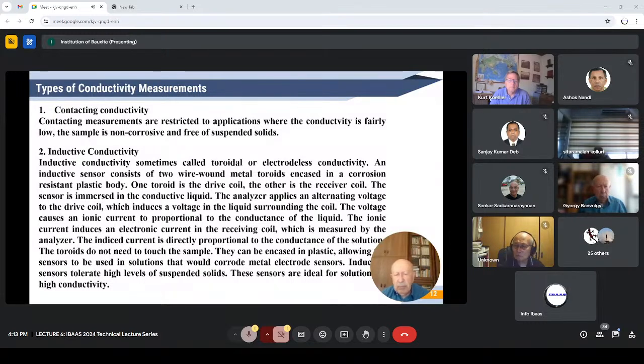Basically, there are two types of conductivity measurements. One is the contacting conductivity. These measurements are restricted to applications where the conductivity is fairly low, the sample is not corrosive and free of suspended solids. This is obviously not the case for the Bayer liquors. The other is the inductive conductivity, which is sometimes called toroidal or electrodeless conductivity.